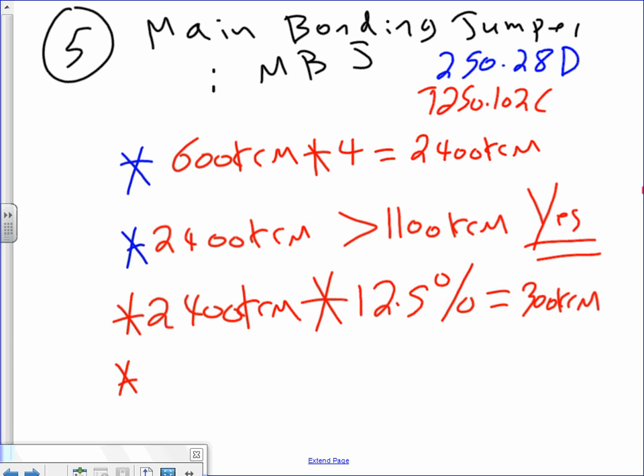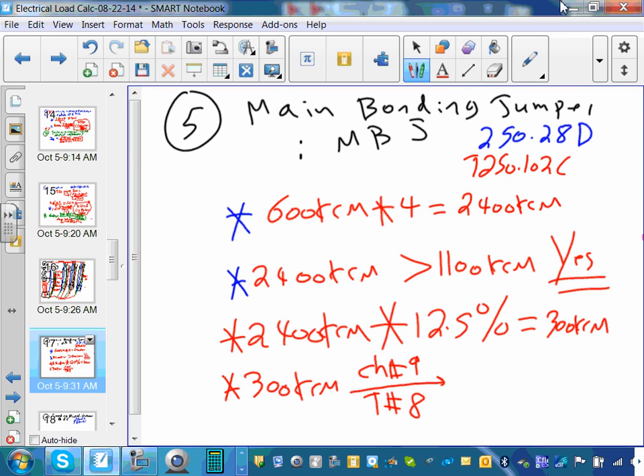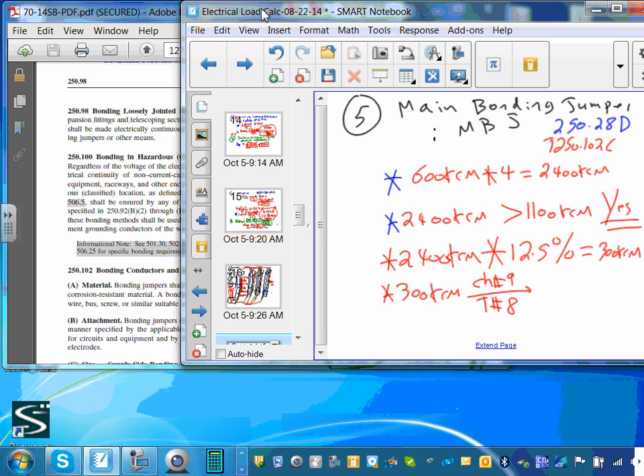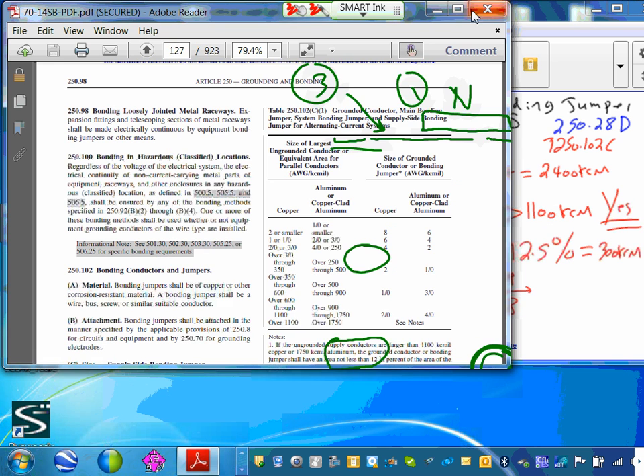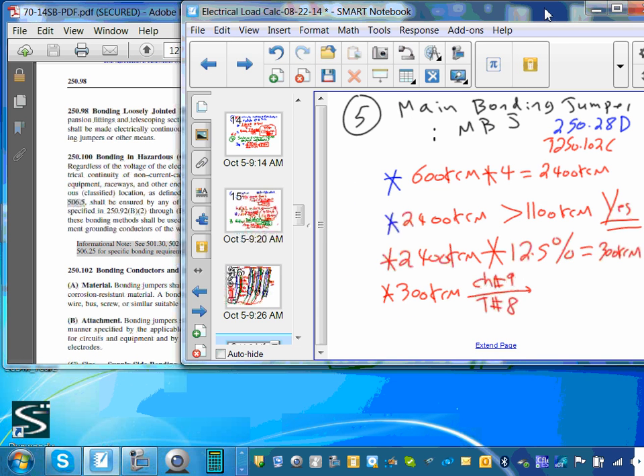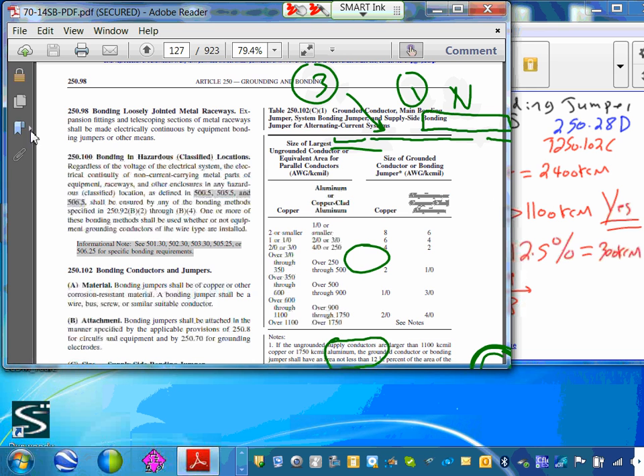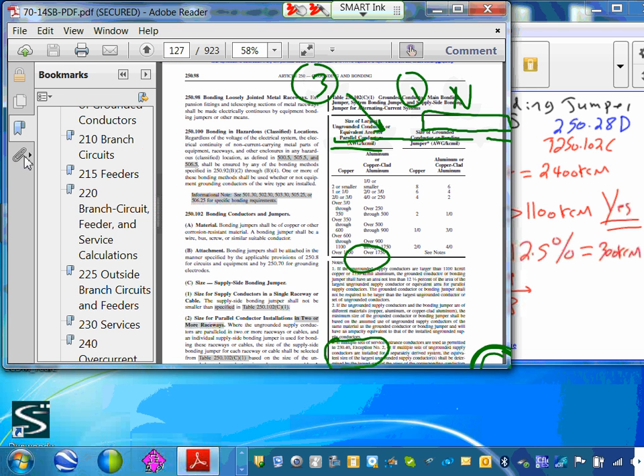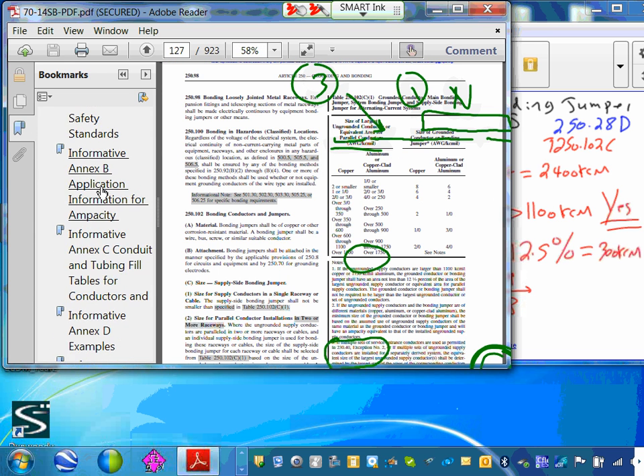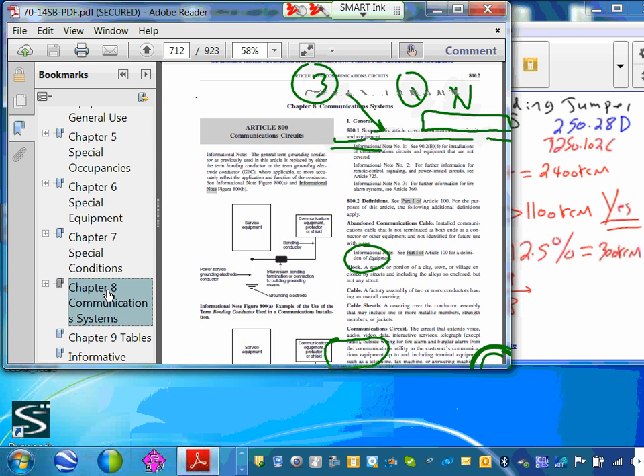Yes, this is what you're going to do. Then you take the 300 KCM, take it to the following. Chapter 9, please. Table 8, please. Let's go to chapter 9, table 8. That's where we do our check. Okay, so we haven't done that. I'm going to move it here. You guys got that? Did I move? Okay, you got it. 300. We're going to go to chapter 9, table 8. Let's go to chapter 9, table 8. Chapter 9, table 8.